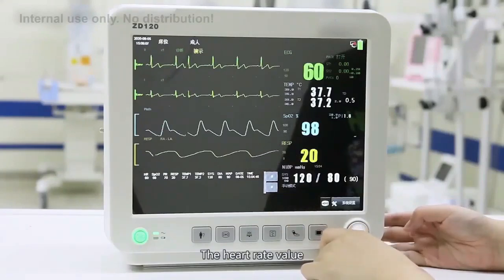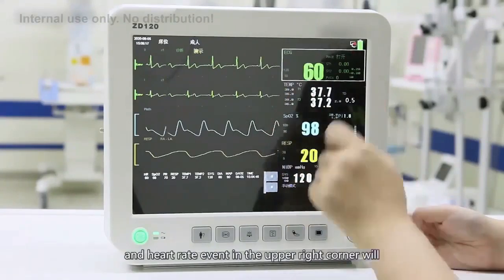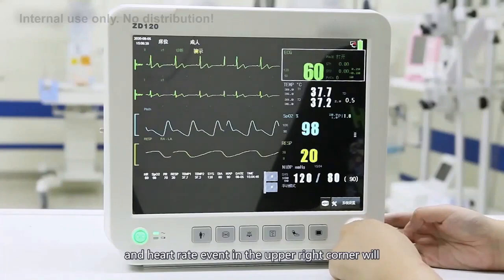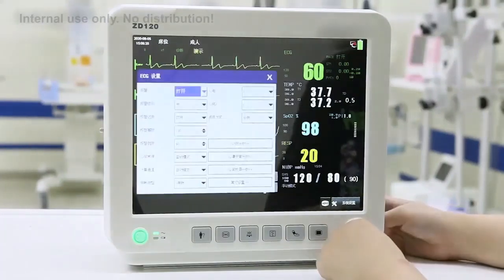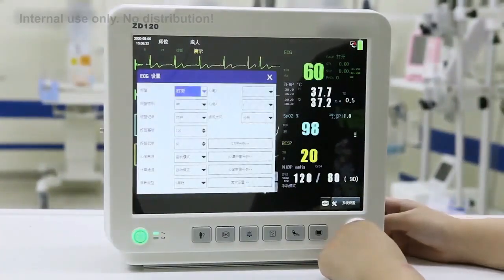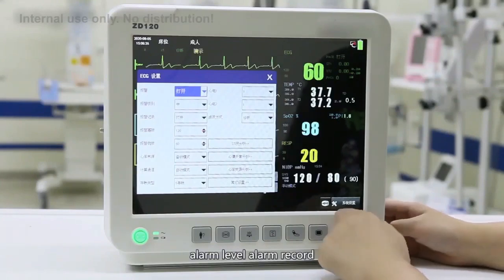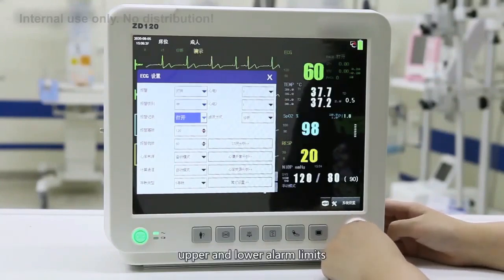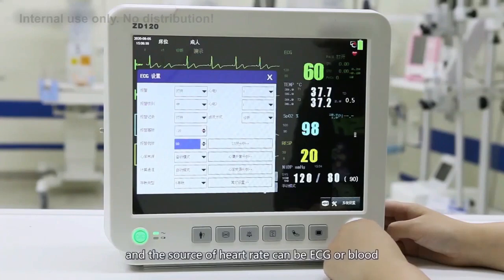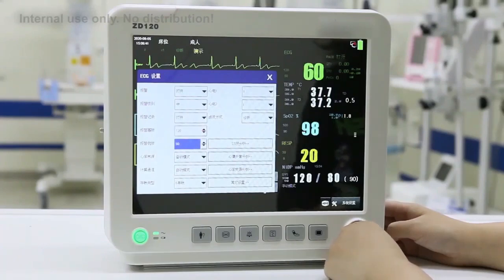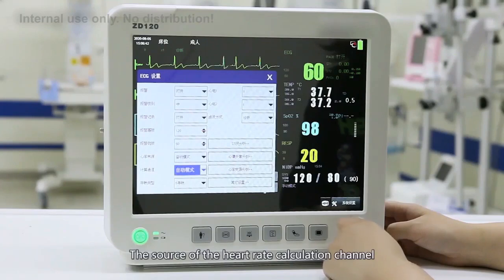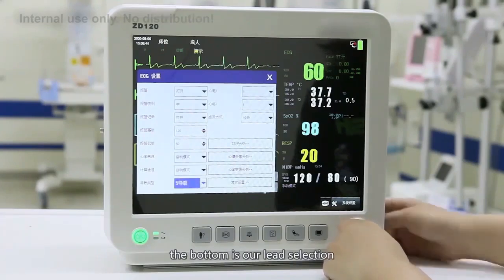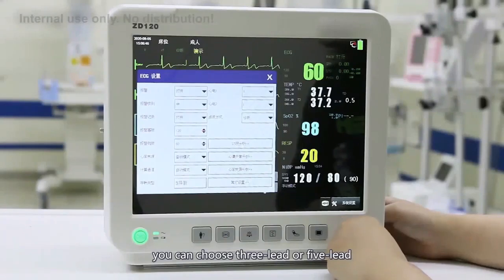The heart rate value, ST segment value, and heart rate event in the upper right corner will enter the setting interface of ECG after selecting and clicking. You can select the alarm switch, alarm level, alarm record, upper and lower alarm limit, and the source of the heart rate can be ECG or obtained by the blood oxygen probe. The source of the heart rate calculation channel; at the bottom is our lead selection. You can choose 3 lead or 5 lead.